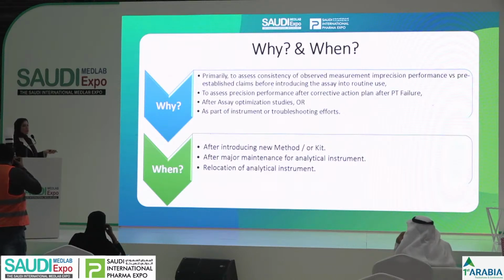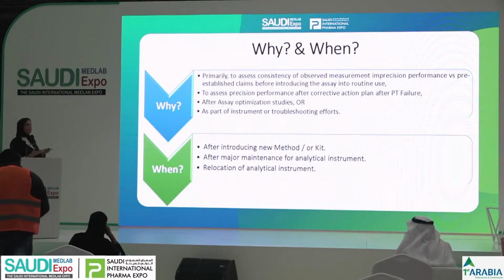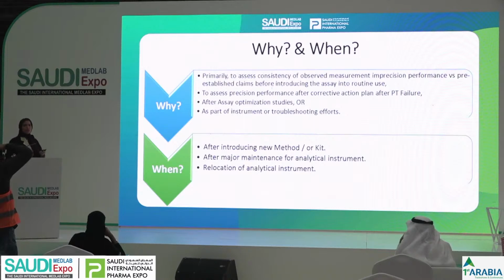The third one, labs always overlook. They don't consider that if I move my instrument, I have to revalidate. Yes, you have to revalidate because some analyzers need readjustment and realignment after installation.